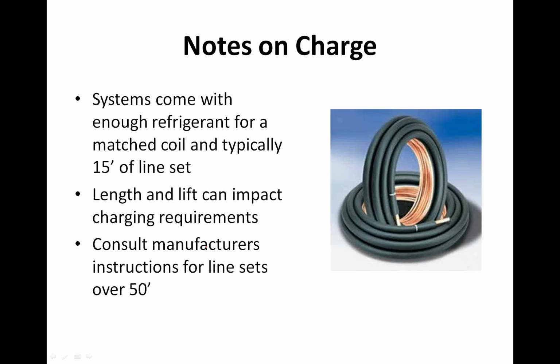It may have 30 feet of line set, 50 feet of line set, or 10 feet of line set. It could be overcharged, it could be undercharged, but unless somebody calls and complains, sometimes the homeowner just figures that's the way it's supposed to operate, that it's supposed to cost them this much money. They just moved into a bigger house, they have no track record with it, so they don't call, and it just runs that way until somebody comes out and properly commissions the system.